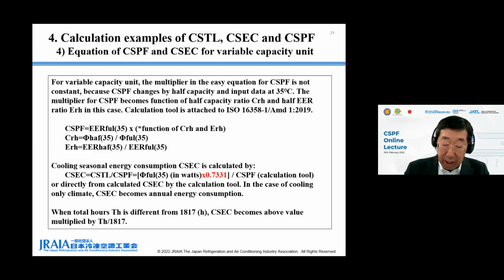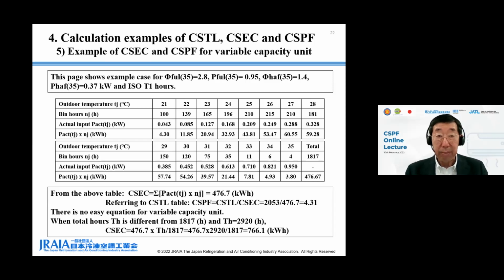In the case of cooling-only climate, CSEC becomes annual energy consumption. When the total hours TH is different from 1,817 hours, CSEC is multiplied by TH over 1,817. Next, please. This page shows a calculation example of CSEC and CSPF for 35 degrees C full capacity 2.8, full input 0.95, half capacity 1.4, and half input 0.37 kilowatt, and ISO T1 bin hours.